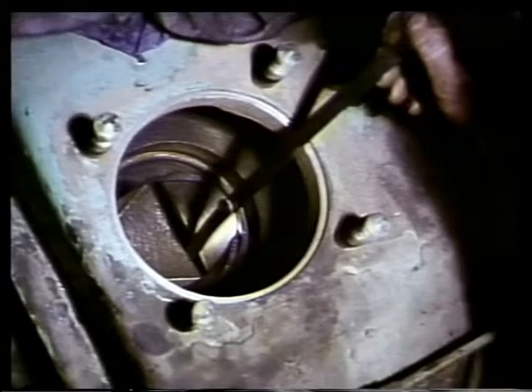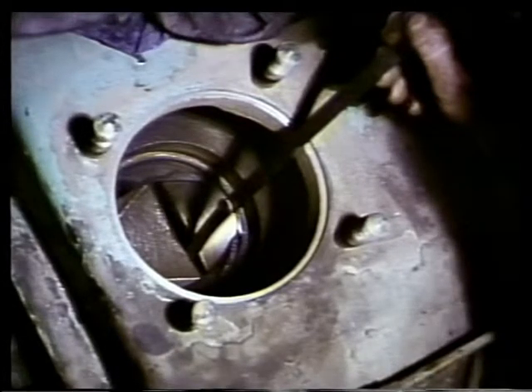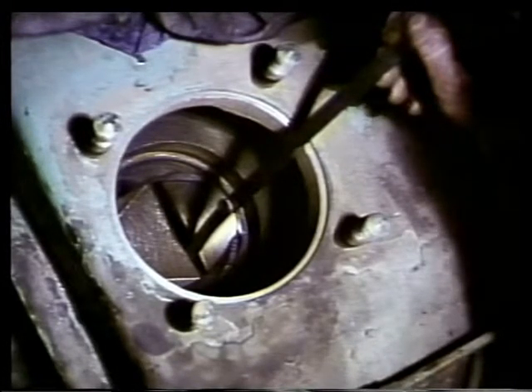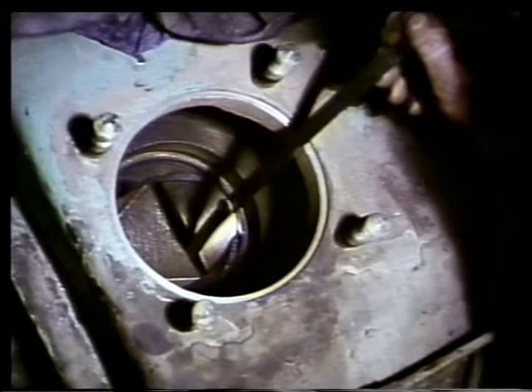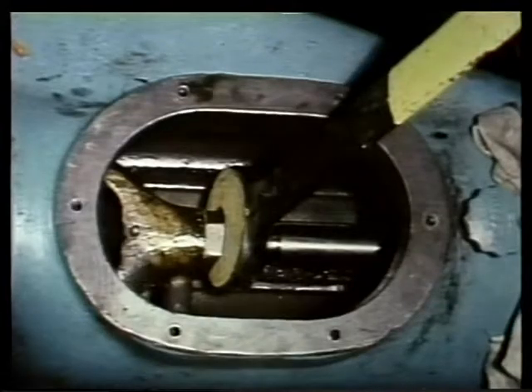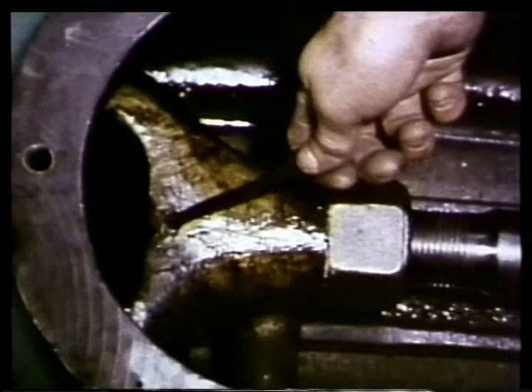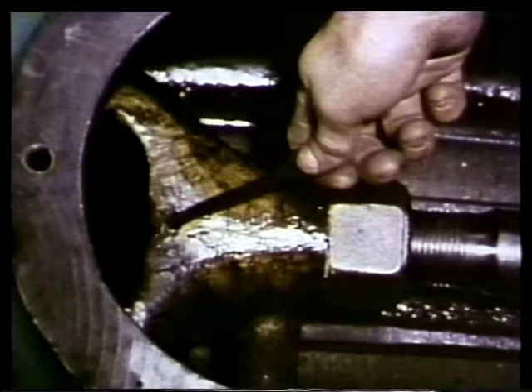Another way to measure piston end clearances is to use feeler gauges instead of solder. This method's covered in your text. When the piston end clearance is correct, tighten the piston rod lock nut and insert a new cotter pin. The lock nut and the cotter pin prevent the piston end clearance from changing when the compressor's in operation.